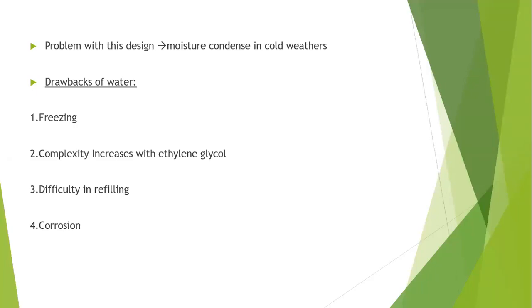Another problem is due to corrosion. With continuous use of tubes with water, the tubes will be corroded. If you refill the water, the empty tubes are filled with air, which increases the rate of corrosion. The water is drained out at night, so some moisture will be present in the tubes. If this moisture combines with the oxygen in the air, it increases the rate of corrosion.